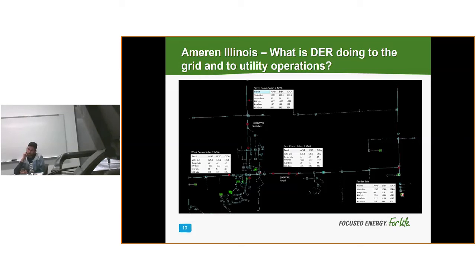Does that make sense? What's the concept of reconductoring? It's just using a different size conductor that could help you reduce or increase the impedance on the line to solve the voltage problem. So you're just controlling the impedance to try to control the voltage drop on the circuit.